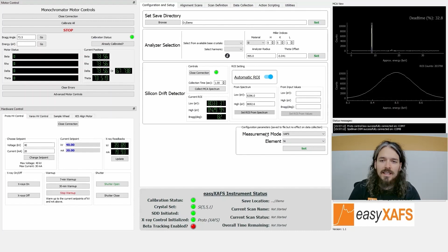That's what we want to use for our measurement. So we set a region of interest around that peak. The plot below that shows the zoomed in view of that ROI. The sum total of that peak is the ROI counts. Here that's about 204,000. That's the number of X-rays that we want to measure, and we measure that at each step in the scan to build up our XAFS spectrum. I'll set the measurement mode to XAFS, select nickel as the element, and then we can move on to setting up a scan definition to do a XANES check on the nickel foil.